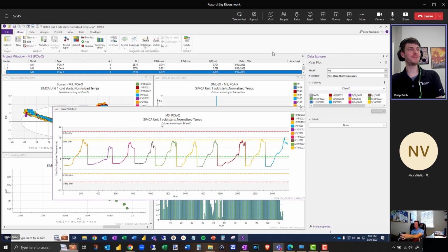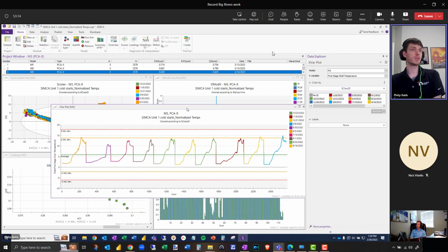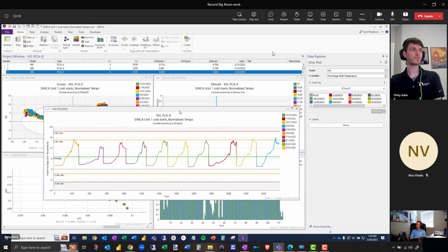Yep, exactly. And that's a really good example of paying attention to the trends it gives you, because you might see a pattern and think, wow, here's my answer. Like, this startup is slower than the other one because look at these temperatures, they're so much lower. And it's like, okay, but this is December and that's June. So you have to think about stuff like that. And it's a very iterative process, right? You start somewhere and then you work through the outliers and any sort of normalization that you need to do, adding variables, taking out variables.